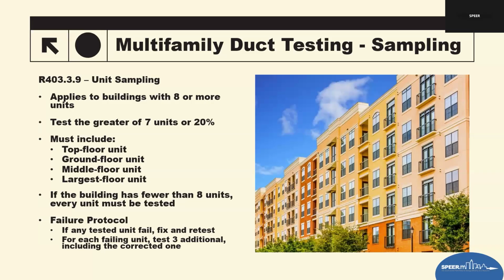I will include a PDF in our survey that is a checklist for plan reviewers, permit techs, field inspectors, and raters to easily digest a sampling protocol. I'll send that with the email we have for the survey. I also want to keep in mind a caveat: the sampling group should be selected either by the building official or by a third party doing compliance testing. The builder, developer, architect, designer, GC, you name it, does not need to select which ones he wants tested. That's a good way to only pass what's being tested and not worry about the rest. It really should be selected by the building official and or third party.